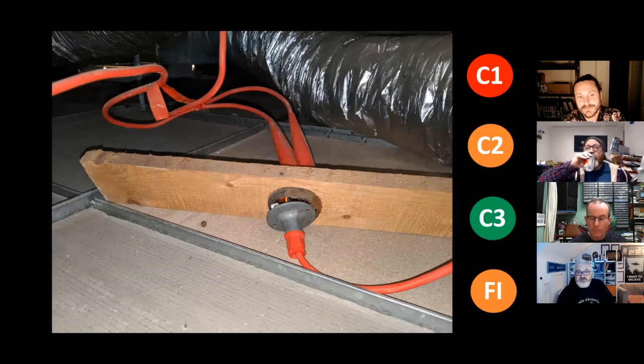Lash up. Words fail me how bad that is, and whoever did that just wants... So they look like MICC cabling. They do. Into the back of what looks like a back entry conduit box. Yeah. With a dome lid, and rather than screwing a hook for a jack chain, they've just screwed an FP200 gland, and no doubt there's a connector in there, or maybe some twisted ends and tape.